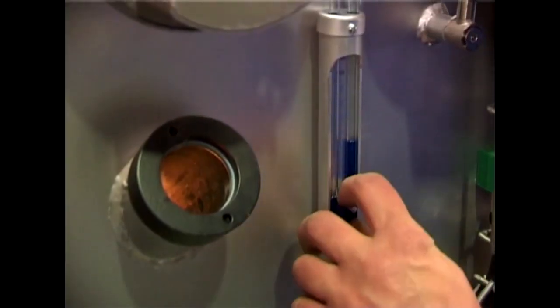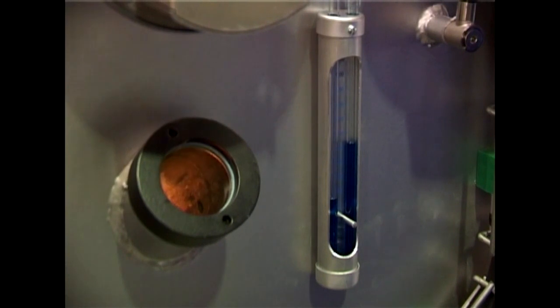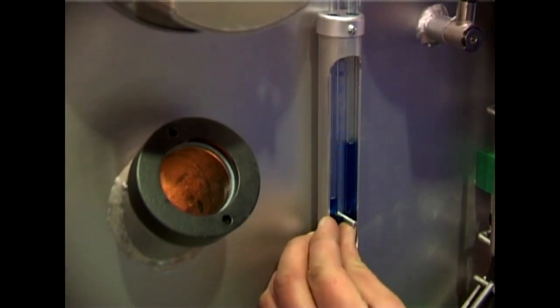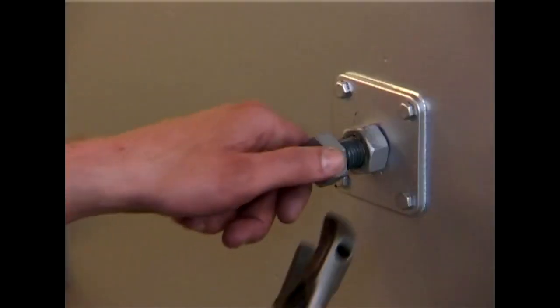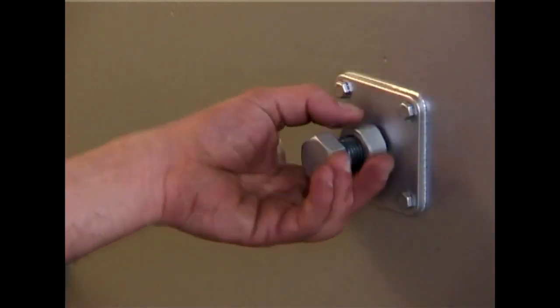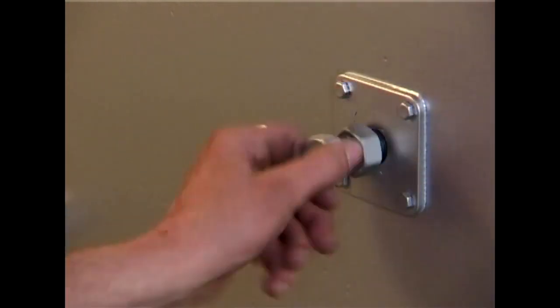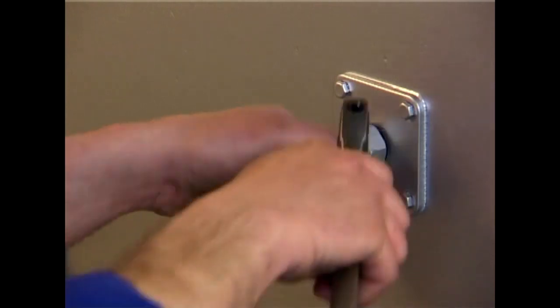You can also try to open the damper on the mixing chamber. This can in many cases increase the vacuum. Finally, you can check the opening of the air nozzles. Closing these with one turn clockwise will increase the vacuum.